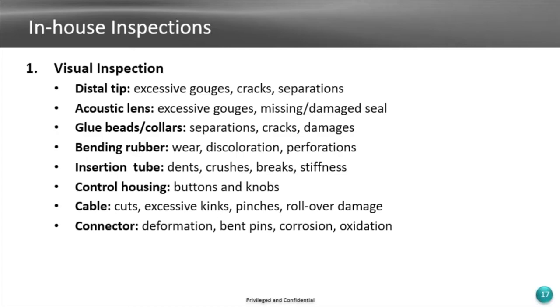And then the connector - look for deformation, bent pins, corrosion, oxidation. This particular probe, a GE probe, is a pinless connector, but these pins can get oxidized if they're exposed to the wrong cleaning materials.